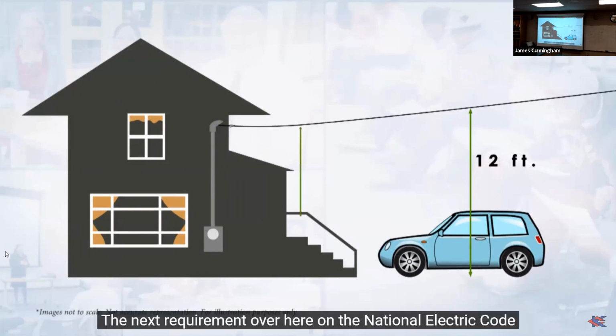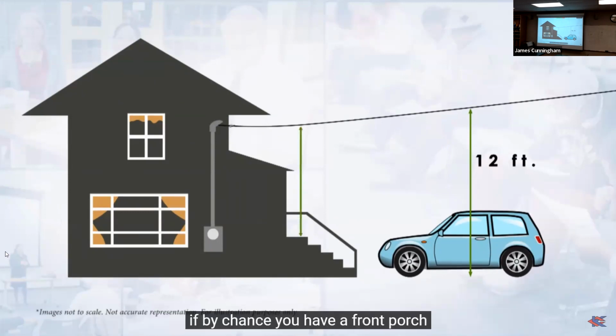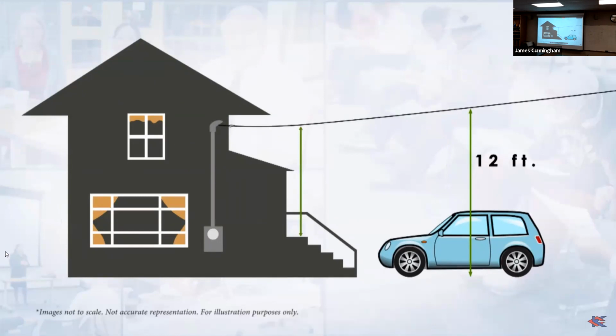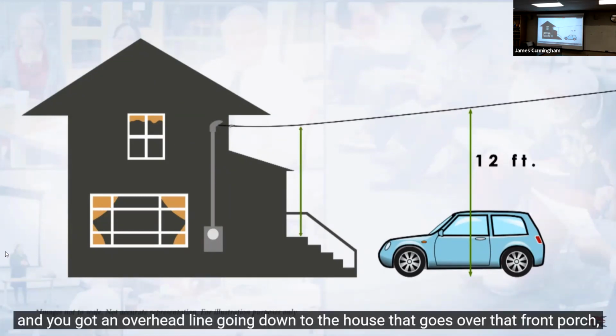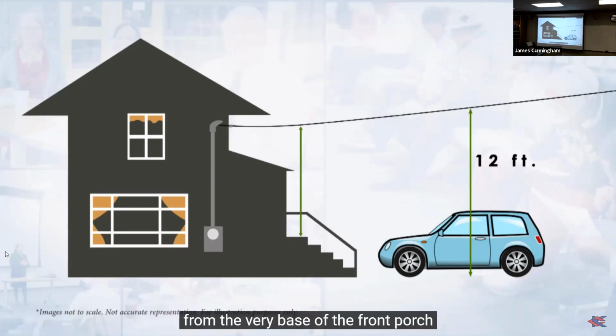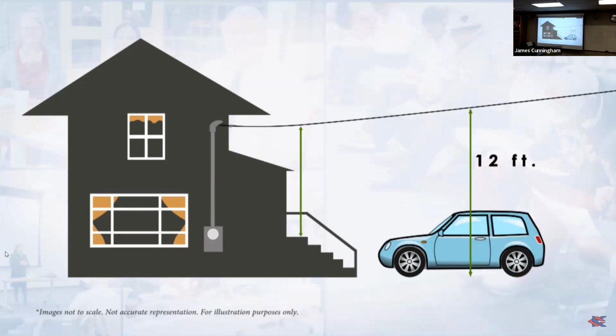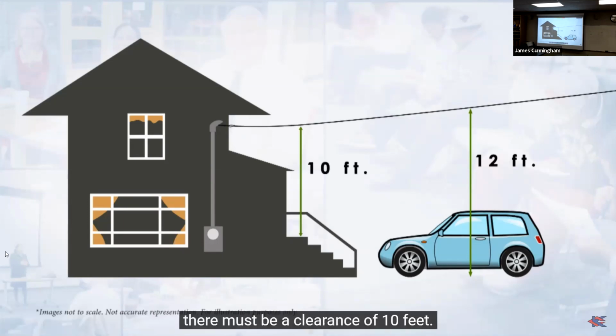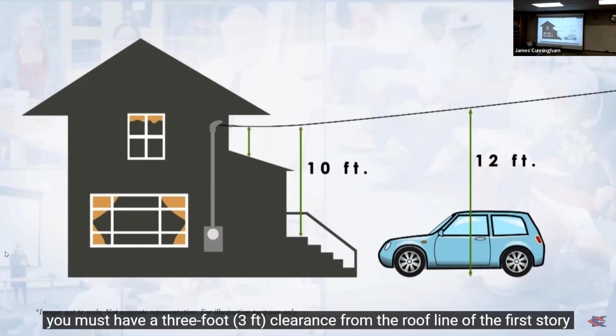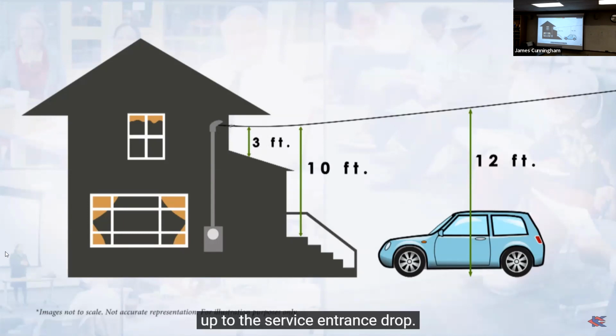The next requirement on the National Electric Code: if by chance you have a front porch and you got an overhead line going down to the house that goes over that front porch, from the very base of the front porch up to the service drop, there must be a clearance of 10 feet. And then if by chance you have a 2-story home, you must have a 3-foot clearance from the roof line of the 1st story up to the service entrance drop.